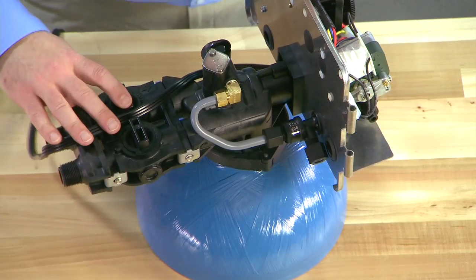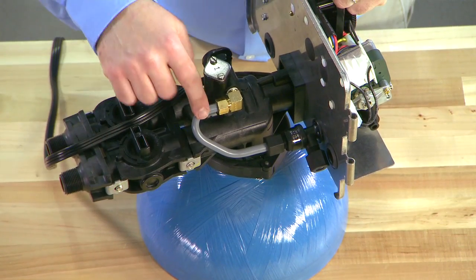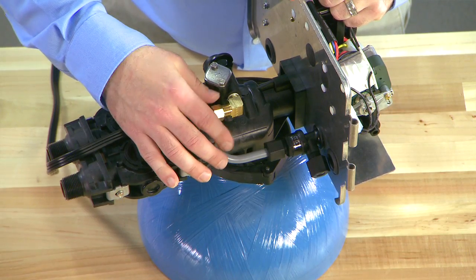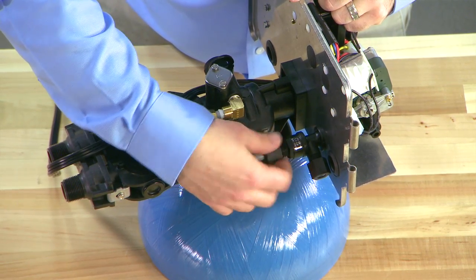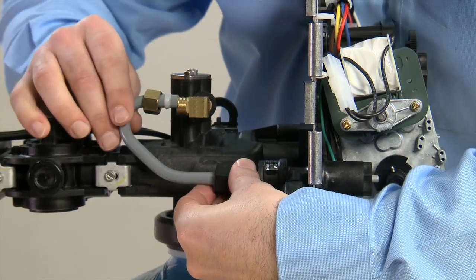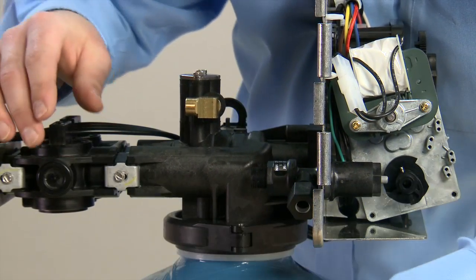To remove the brine valve from the 2510 valve, we begin by loosening the nuts on the J-tube. First from the connection up by the injector and second from the brine valve itself. Once loose, we pull the J-tube towards the rear in order to remove it.